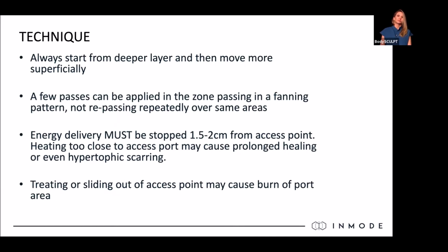Fanning, making sure, three things I tell the practitioners and that you want to keep an eye on. Number one, keep it moving. You don't want to have the instrument stopped. You also want to only heat the area. You don't want to heat proximally to the access incision, just like you don't want to over-liposuction within a centimeter or two of the access incision. Number three, keep it deep. You should always have a little bit of water and a little bit of tissue between the under surface of the skin and the internal probe. Anything else? No, that's good.